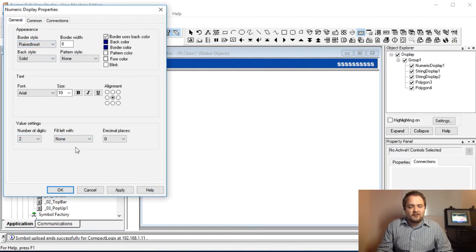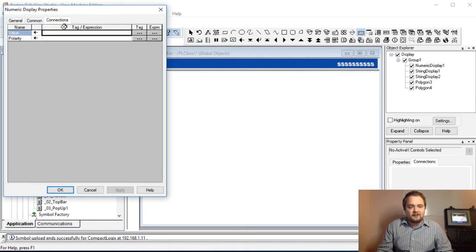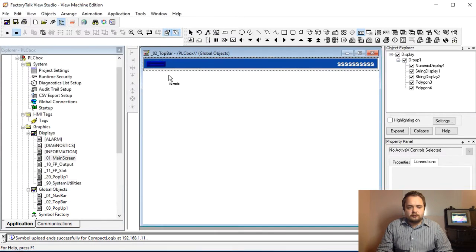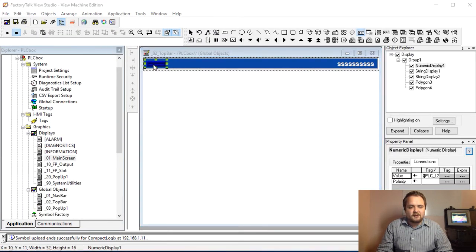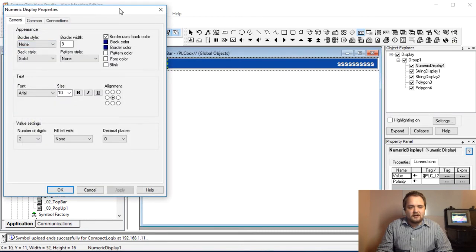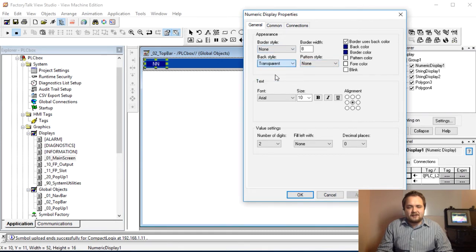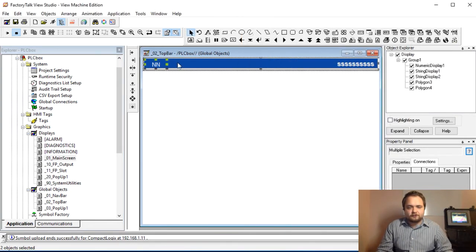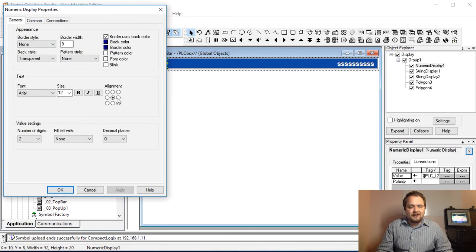Under Object — Numeric Display — we start with hours: number of digits is two, no decimal places, fill left with none. We connect it right away to the hour tag. We set the border to none and back style to transparent so it's essentially invisible as a container. I'll adjust the fonts to match the rest of the interface, align it to the right, and make the width about 30.